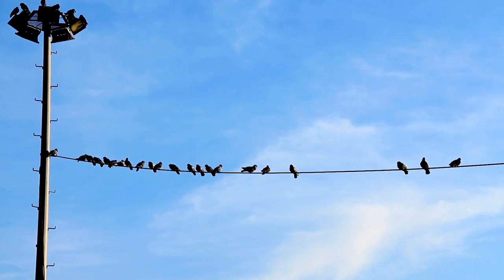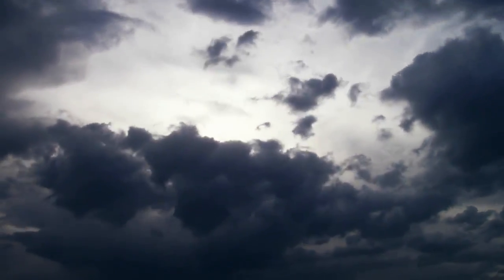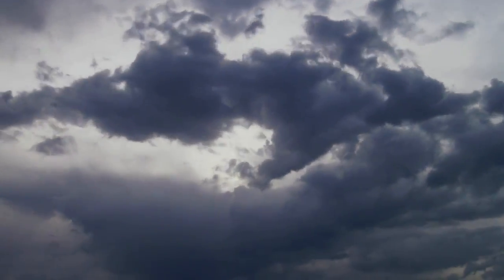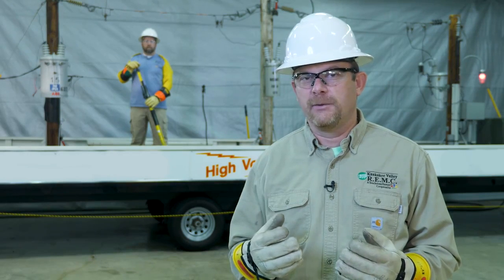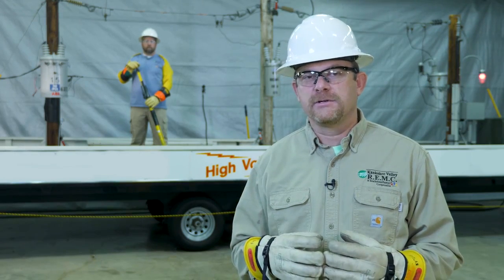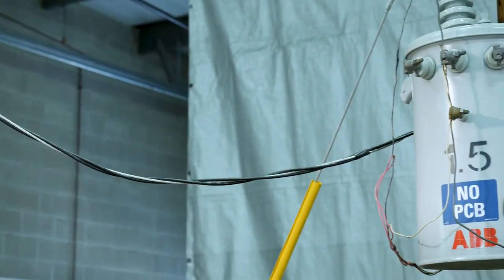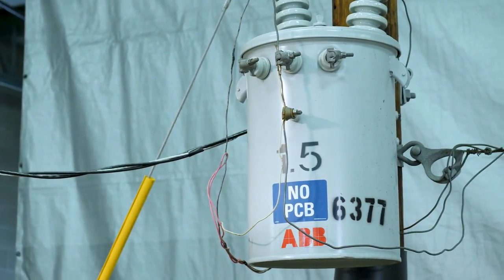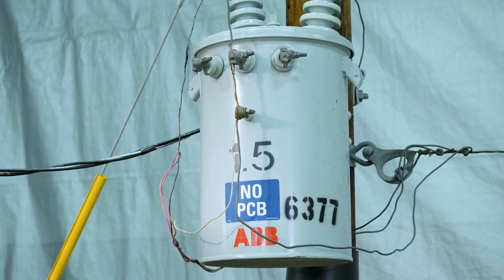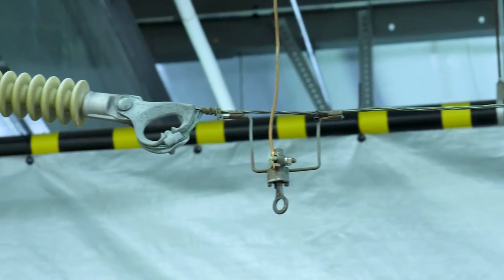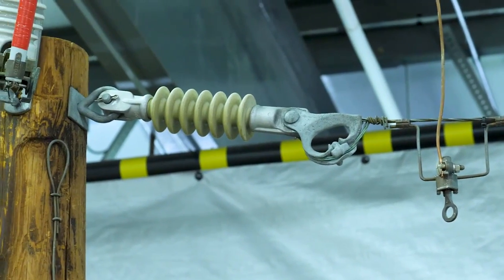So you're sitting at home on a beautiful sunny day and your lights go out. We often associate a power outage with a thunder or a windstorm, but there really are many things that can actually cause an outage. One of these being animals that can access the equipment on a power pole. The transformers and reclosers mounted on the poles are connected to the neutral wire, which is the bottom wire between the poles. It's the wires that are connected to the bushings on the top of the transformers or reclosers that are energized.